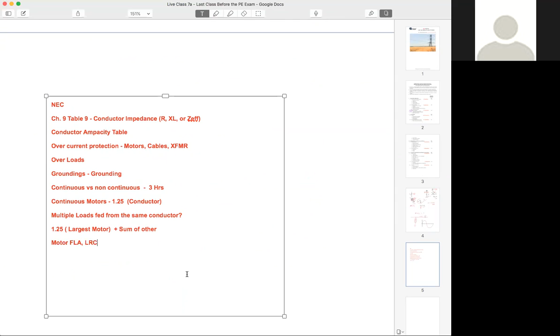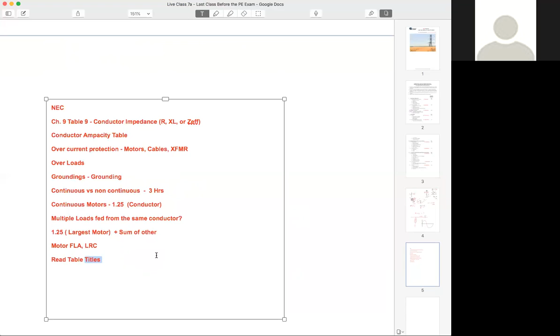Read table titles. There are many different types of slightly different tables. Check for the voltage rating, power rating, temperature rating, right? Don't use ampacity for a cable that's in free air if it's actually in conduit, et cetera. So really make sure you're looking at the table titles and interpreting the differences.